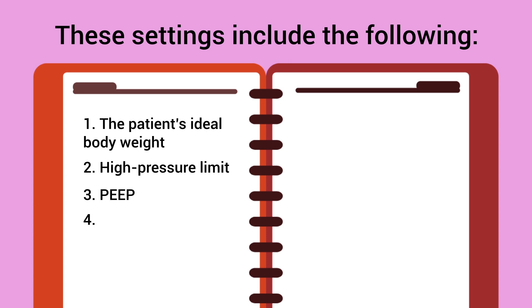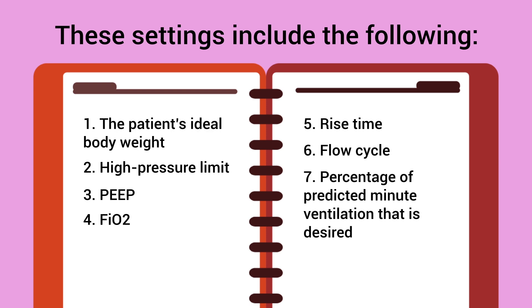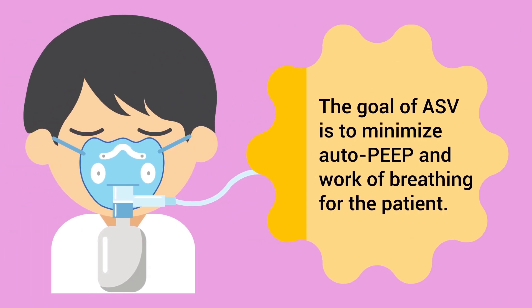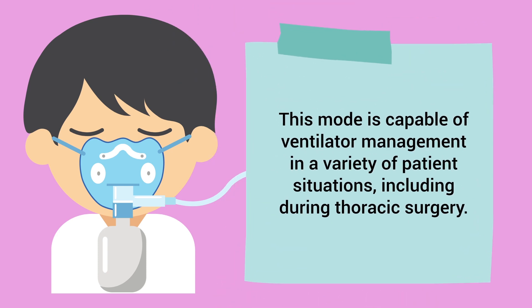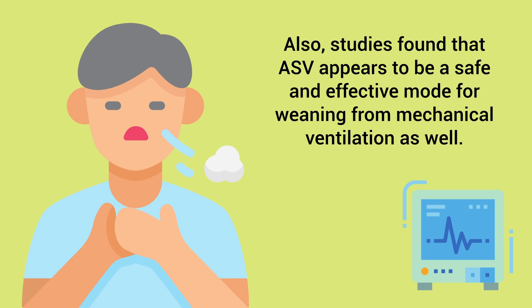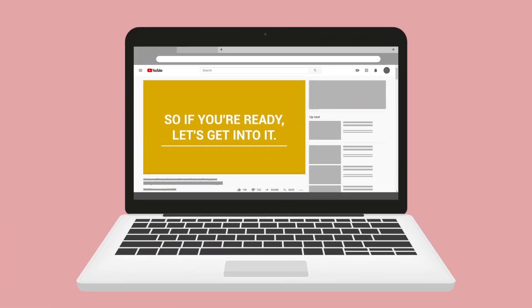Settings entered by the practitioner include the patient's ideal body weight, high pressure limit, PEEP, FiO2, rise time, flow cycle, and the percentage of predicted minute ventilation desired. The goal of ASV is to minimize auto-PEEP and work of breathing for the patient. This mode is capable of ventilator management in a variety of patient situations, including during thoracic surgery. Studies also found that ASV appears to be a safe and effective mode for weaning from mechanical ventilation.